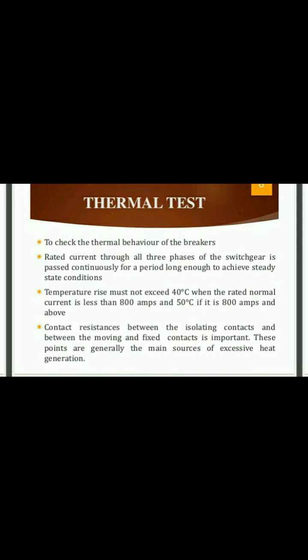Rated current, in all three phases of the switchgear, is passed continuously for a period long enough to achieve steady state conditions. Temperature rise must not exceed 40 degrees Celsius when the rated normal current is less than 800 amperes, and 50 degrees Celsius if it is 800 amperes and above. The contact resistance between the isolating contacts, and between the moving and fixed contact, is very important. These points are generally the main source of excessive heat generation. So this is called a thermal test.